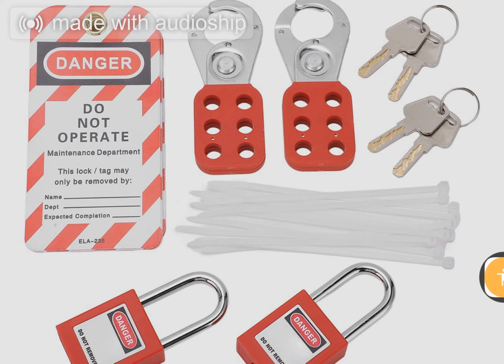And shouting, don't touch that, isn't enough. Lockout means you use a physical padlock to lock the breaker in the off position. A literal lock. And this is the crucial part: you keep the key in your pocket. It physically prevents the circuit from being energized.